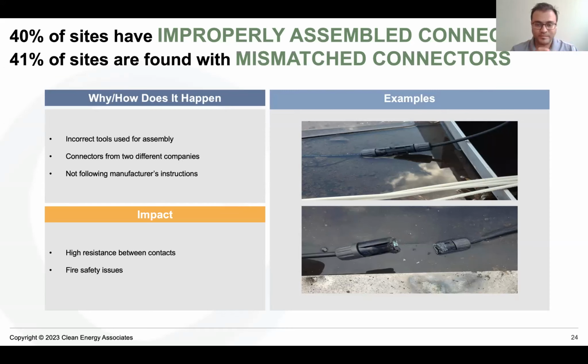In industry there's a popular word called MC4 compatible, which is funny, because compatibility just means the plastics fit. It doesn't refer to matability or long-term usage of these connectors. If connectors from two different manufacturers are mated, they aren't tested, and the UL listing doesn't cover testing with two different manufacturers.